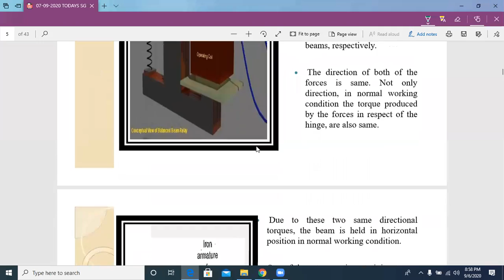Here is the diagram, the same diagram. From an exam point of view, we can draw the diagram like this. Okay, so it is a spring. The spring is responsible for the restraining torque, and it is a coil, a magnetic coil, and it is responsible for the operating torque. In the normal case, both the torques are equal. When the fault happens, the magnetic coil produced torque dominates the spring torque. Due to that reason, this particular beam moves downwards. When this beam moves downwards, these two contacts are closed.